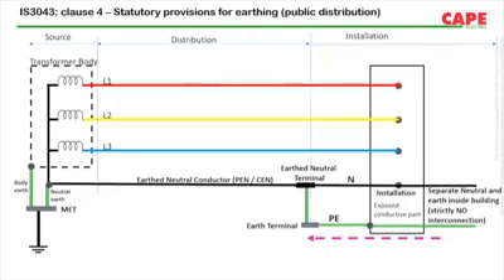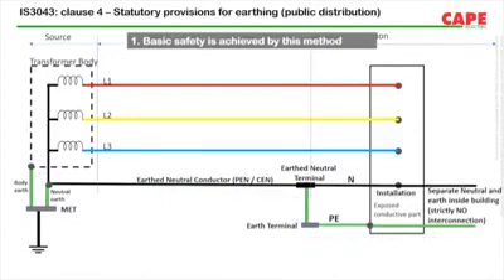Basic electrical safety is achieved in this method. Fault current in the installation returns back to the source through the earth terminal, through the link between the earth and neutral, and through the CEN conductor to the neutral of the source. Depending upon the fault loop impedance, enough fault current flows and disconnects the supply in case of a fault in the installation.